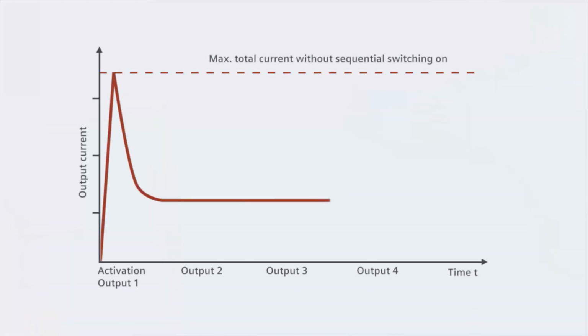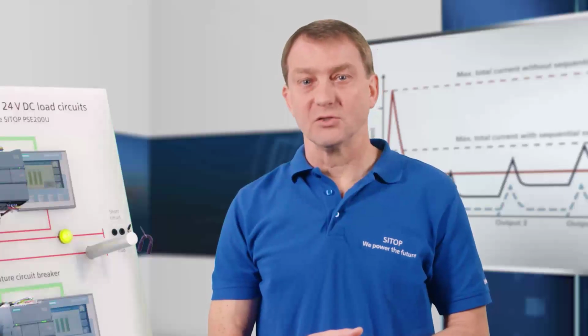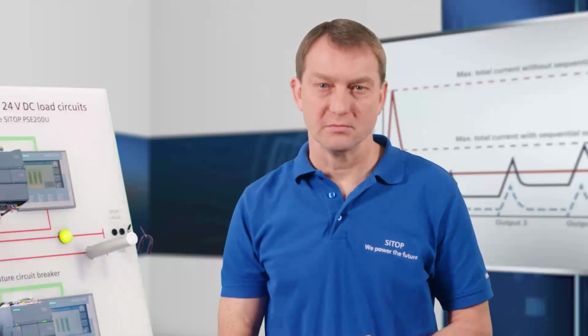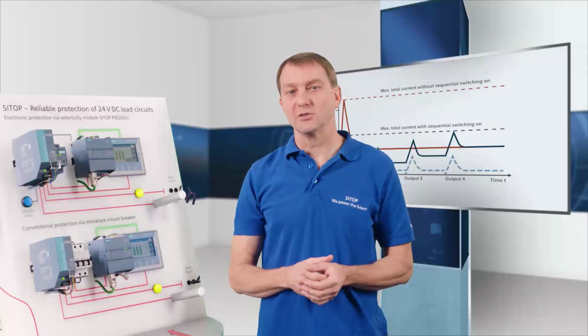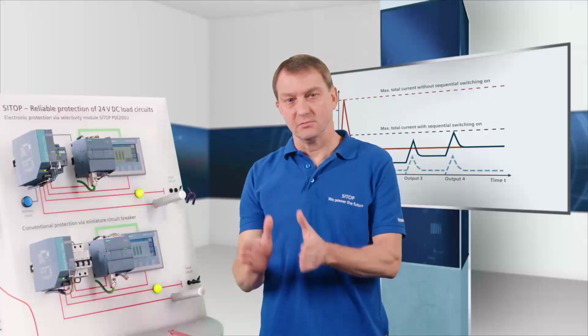Another advantage is the sequential connection of the outputs, which enables you to reduce the size of the power supply. As you know, a power supply is primarily dimensioned according to the inrush currents of the loads. To minimize the summation current of the individual inrush currents, the outputs can be connected with a delay.